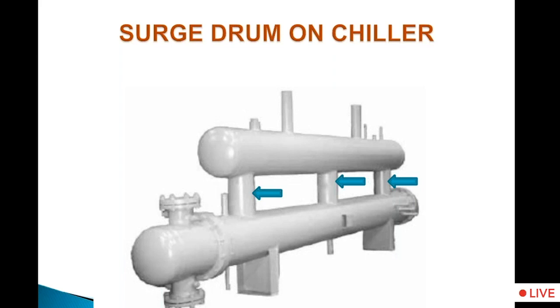I will give you an example. In Ahmedabad, I visited one plant where people said that if they use 6-cylinder compressors, no liquid comes to the compressor. But if they use 9 cylinders, there is a liquid stroke. Now they thought they needed to change the diameter of the surge drum, which is a wrong theory.